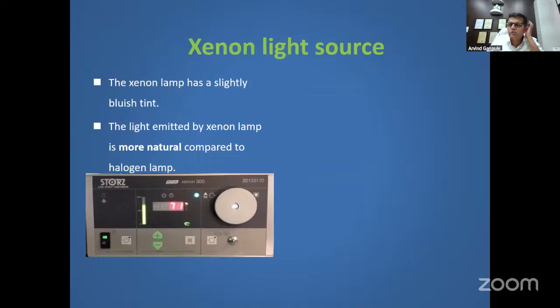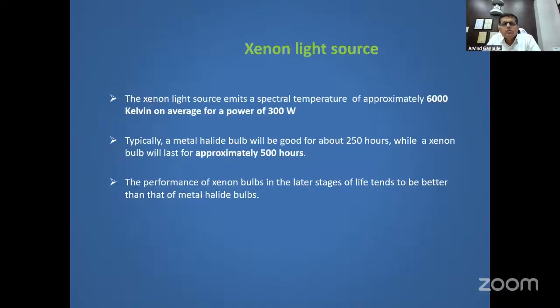So then came the xenon light source, and the xenon had a slightly bluish tint, but it was more natural. And this is the typical equipment you will see on the trolley. The xenon emits a spectral temperature of approximately 6000 Kelvin with an average power of 300 watt. And you remember the halogen, it was just 150 watt. But again, see the major difference. The halogen was just 200 hours. Here it is increased to 500 hours. So it becomes more cost effective, more economical. The light emanated is better. So that is the reason that they came into picture.